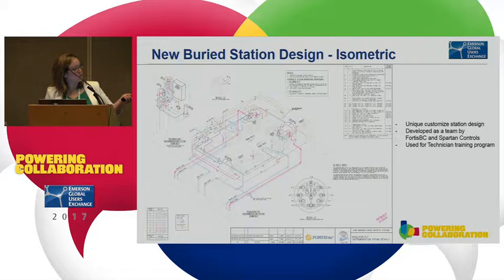And the other interesting thing is here's your monitor, this is your overpressure protection. We're running all of this tubing directly into the pipeline, so we're in a nice stable spot. Anyone who's ever put in a pressure transmitter knows you have to put it in a nice stable spot, or you don't get a very good reading.